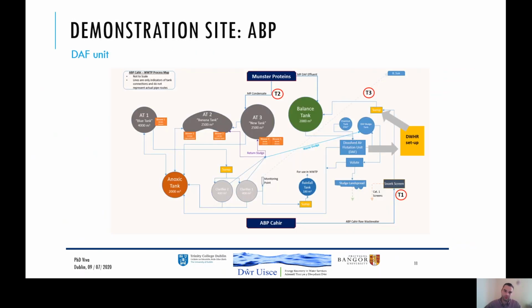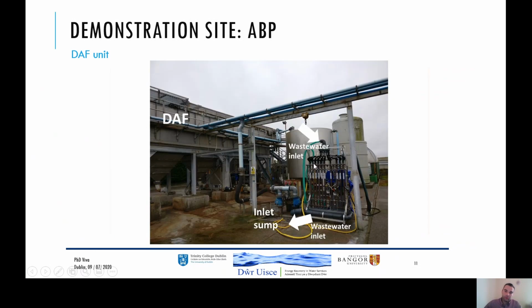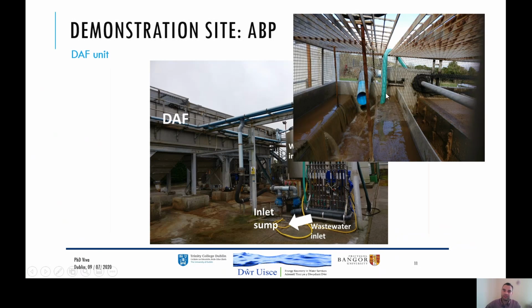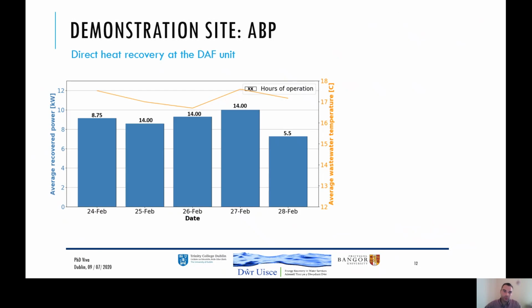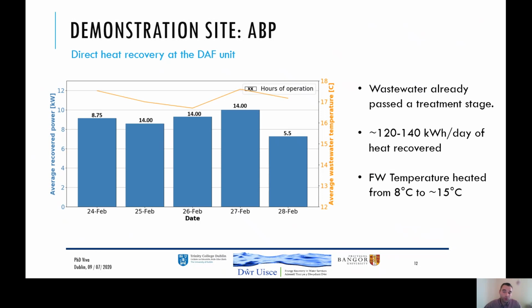The second demonstrator was in the wastewater treatment system of a meat processing factory, where we got the wastewater out from the dissolved air flotation unit into our heat recovery device and then dumped it back into the inlet sump. So we can see here the DAF unit here. The water is let into the top of our wastewater heat recovery device and then let out here back into the sump. Here you can see the pump that leads us to our device in the DAF unit. And here we saw, in this week of operation, a heat recovery power ranging from 8.5 to 10 kilowatt and about 120 to 140 kilowatt hour per day of recovered heat.